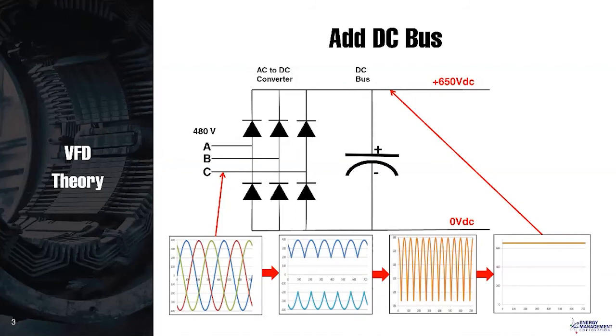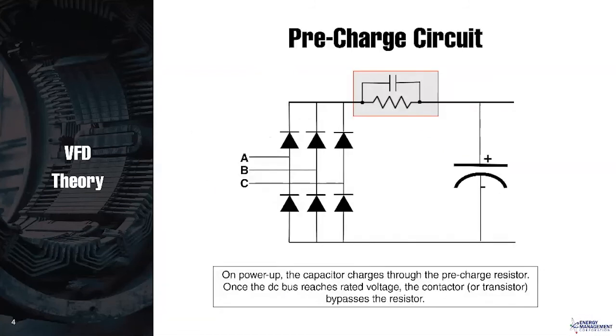You can test that capacitor if a drive has not been used for more than, let's say, maybe a year or so. Most manufacturers will recommend that you reform that capacitor, and that includes application of lower than rated voltage in order to bring that up to speed. We won't get into that in detail this time, and different manufacturers have different recommendations. If the drive is running, then if you measure from the positive to the negative bus with your meter in AC mode rather than DC, you should see a very low ripple, say less than 3 volts in a properly functioning drive.